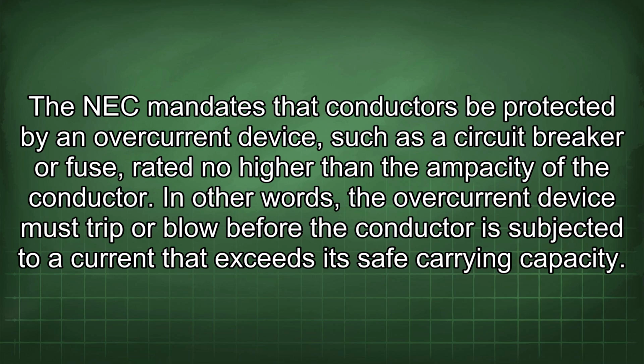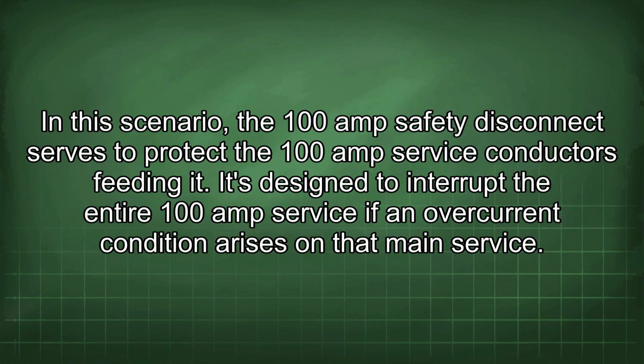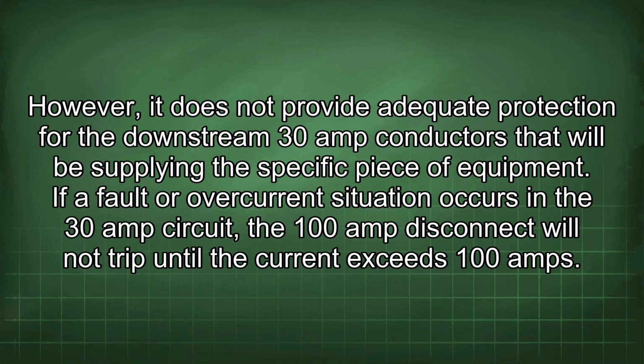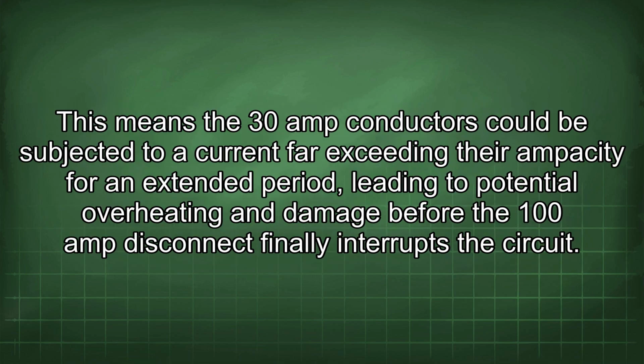In other words, the overcurrent device must trip or blow before the conductor is subjected to a current that exceeds its safe carrying capacity. In this scenario, the 100 amp safety disconnect serves to protect the 100 amp service conductors feeding it. It's designed to interrupt the entire 100 amp service if an overcurrent condition arises on that main service. However, it does not provide adequate protection for the downstream 30 amp conductors that will be supplying the specific piece of equipment. If a fault or overcurrent situation occurs in the 30 amp circuit, the 100 amp disconnect will not trip until the current exceeds 100 amps. This means the 30 amp conductors could be subjected to current far exceeding their ampacity for an extended period, leading to potential overheating and damage before the 100 amp disconnect finally interrupts the circuit.